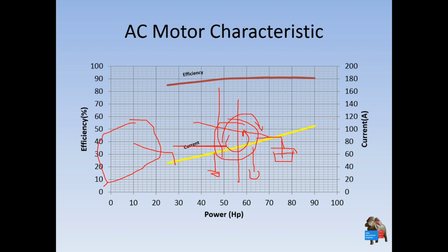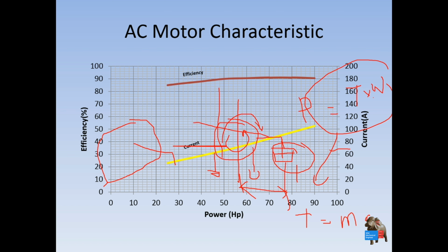And when it is balanced, you measure how much weight you put to make it balance, and the distance from the center line, which you keep fixed all the time. Then the power will be torque multiplied by RPM, and this torque will be equal to the mass of this counterbalance multiplied by the arm length. This is considered as how much power is actually transferred by the motor into the pump.